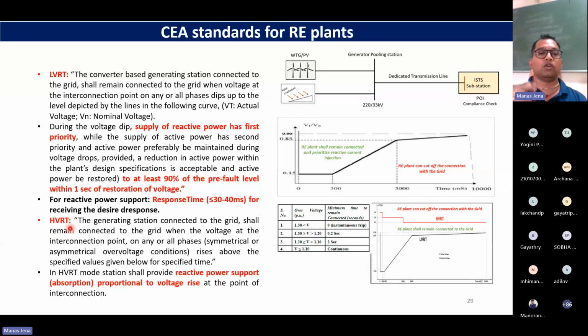Similarly, HVRT, high voltage ride through. If there is high voltage, naturally we understand we don't need to provide VAR, rather we need to absorb VAR. So the generating station connected to the grid shall remain connected when the voltage at the interconnection point on any or all phases rises above the specified value given in this curve. You can see this red colored HVRT, and the values are given. If the voltage is more than 1.3 per unit, no need to remain connected. It is a very dangerous situation for you also, so you will trip instantaneously. Voltage between 1.2 and 1.3, the time limit is 0.2 seconds. 1.1 to 1.2, 2 seconds. Voltage less than 1.1, you have to stay connected continuously. This is what is referred to as the HVRT requirement.